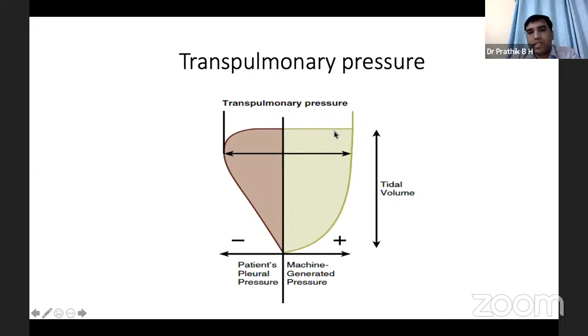Let us see this graph. In the first breath, the tidal volume delivered is based on the peak inspiratory pressure given by the ventilator and also the negative intrathoracic pressure generated by the baby. So the tidal volume delivered is more than what is required for the baby. In the second breath, the ventilator decreases the PIP compared to the previous breath, and the patient has taken a lesser spontaneous effort, though not as high as in the previous breath. So again, the tidal volume delivery is okay.